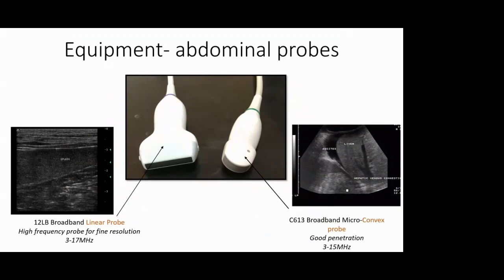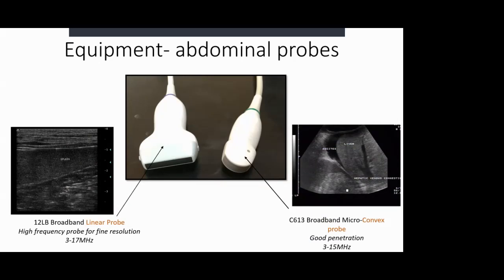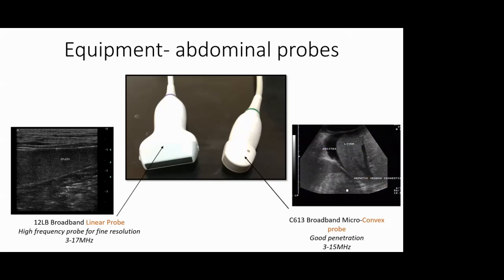If you've got the luxury of having a second probe, I would be thinking about having a linear probe like this one here, and that would be a higher frequency probe. So higher frequency probes run at a higher frequency, and what they do is they allow you to see fine detail. So they're good for fine resolution, but that is at the expense of the depth. High frequency probes are maybe not so good at penetrating deep into tissues.